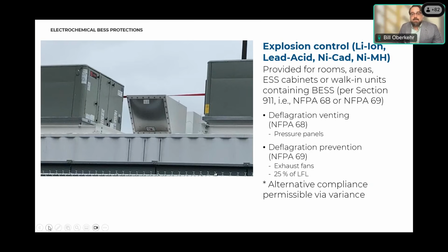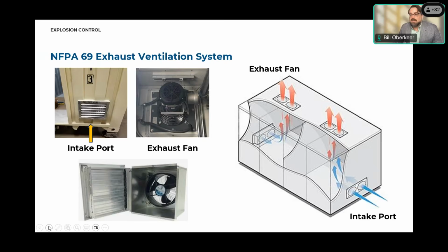We've got flammable gas exhaust ventilation systems as well. This is part of the NFPA 69 explosion prevention. These are also called combustible concentration reduction systems. Air intake is generally best toward the bottom of enclosures to ensure airflow through the overall interior, and the system pulls hot gases up and away from the enclosures. So, a simple exhaust system. Next slide, please.